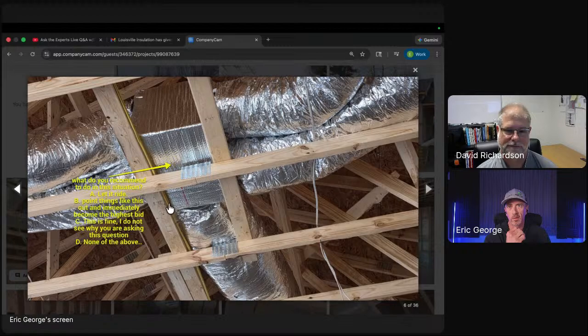The better thing to do would be to remove all this bubble wrap and spray closed cell directly to the sheet metal and to the collars on the flex duct. That would seal it really well and insulate it a lot better than this Reflectix you've got here.